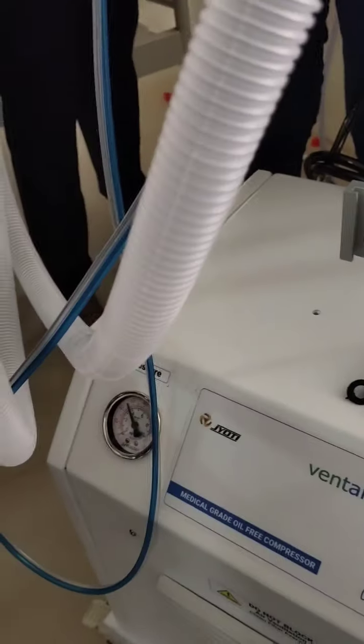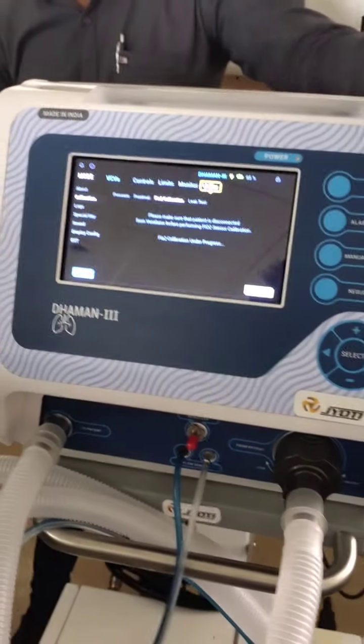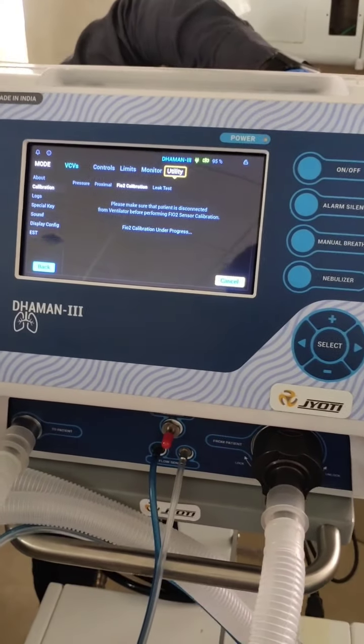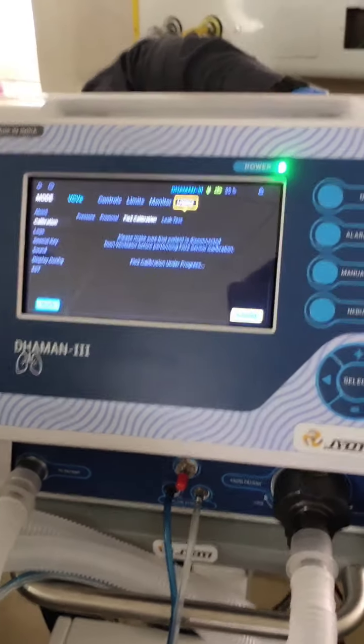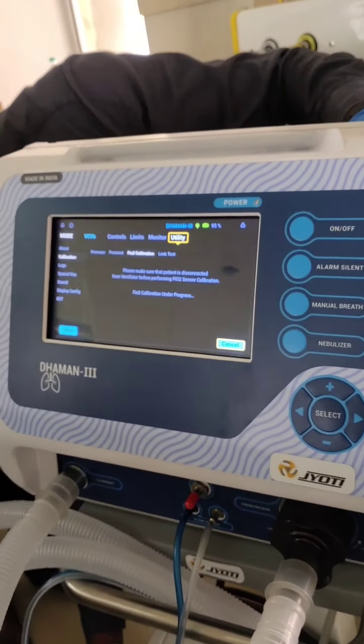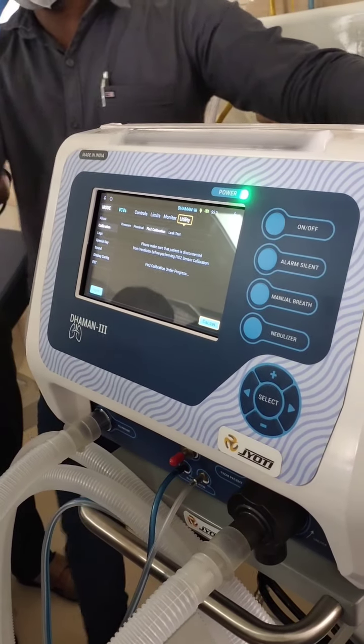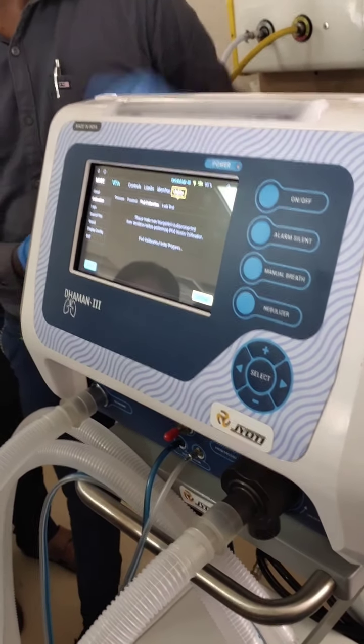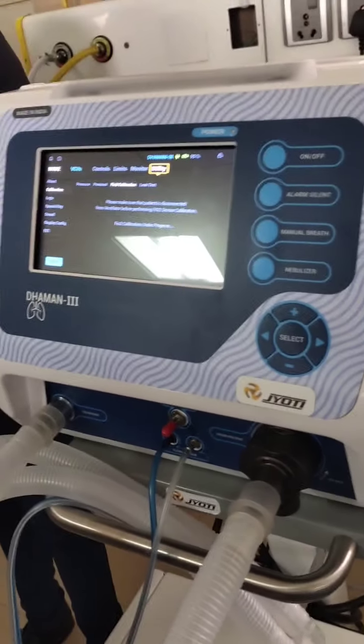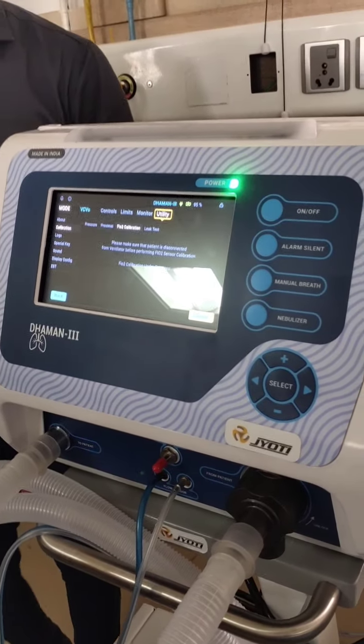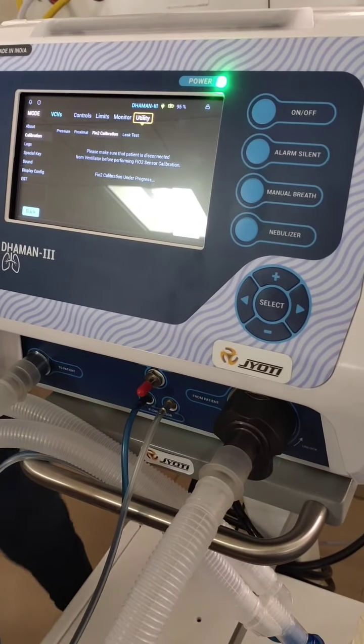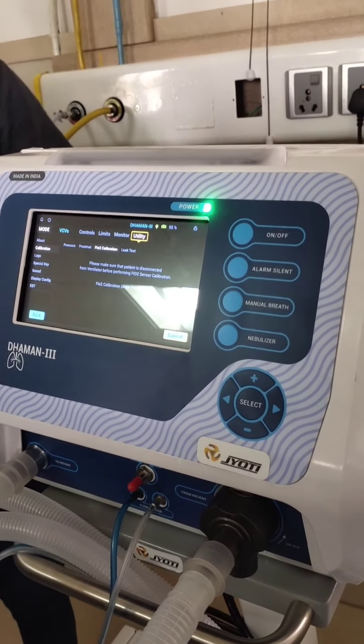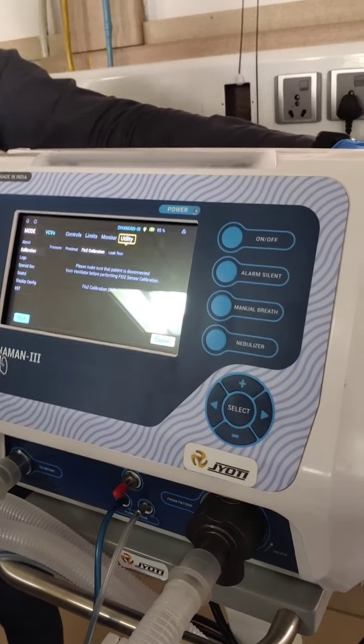It does not happen with all the instruments, maybe only 1 or 2, so you have to check. That is because of the solenoid. The solenoid moves in forward and reverse direction and gets stuck in one position. At that time the pressure will not get developed. If you close that, the solenoid will come to the opposite direction and start developing pressure. More than 40. Yeah, these are just troubleshooting steps for your information. It won't usually happen, but if it does, you have to handle it. These are the normal troubleshooting steps we do outside. Other than that, you should not do anything.